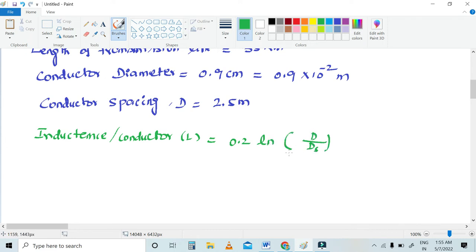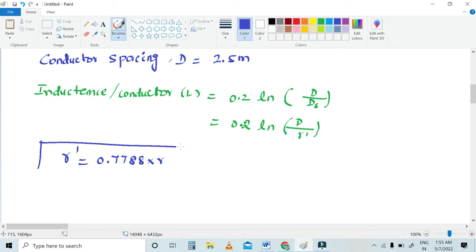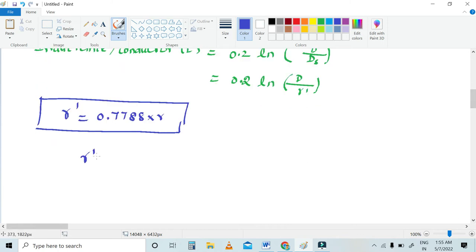The inductance formula is L = 0.2 ln(D / r'), where r' is the geometric mean radius (GMR). The r' is calculated as r' = 0.7788 × r.